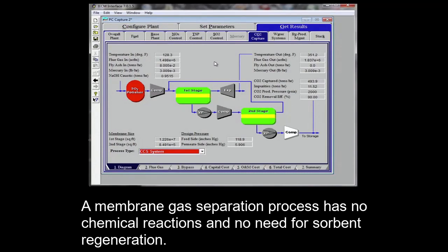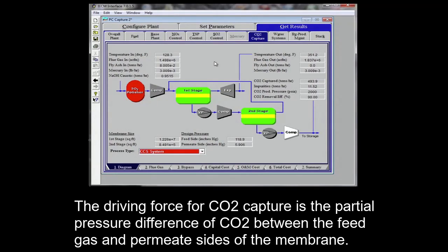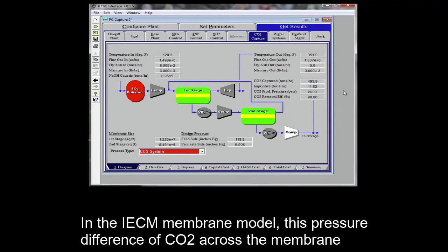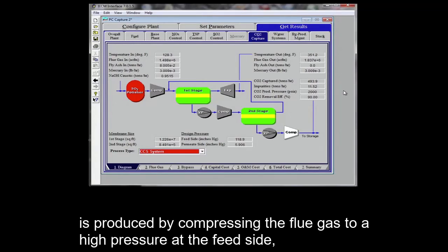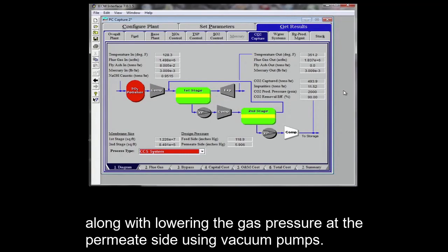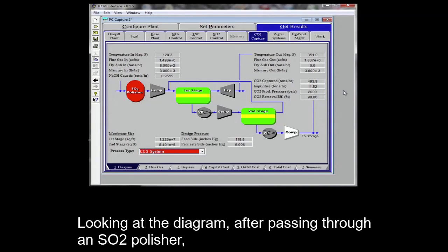A membrane gas separation process has no chemical reactions and no need for sorbent regeneration. The driving force for CO2 capture is the partial pressure difference of CO2 between the feed gas and permeate sides of the membrane. In the IECM membrane model, this pressure difference of CO2 across the membrane is produced by compressing the flue gas to a high pressure at the feed side, along with lowering the gas pressure at the permeate side using vacuum pumps.